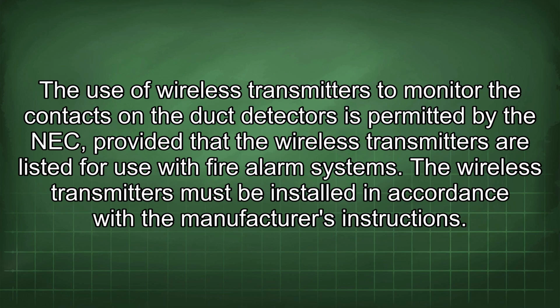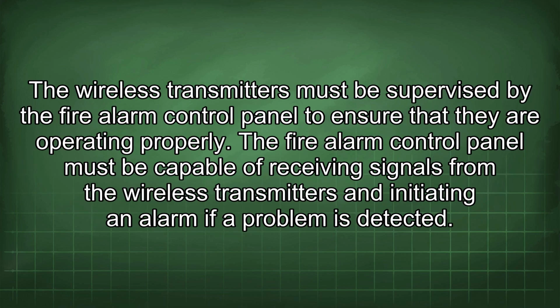The use of wireless transmitters to monitor the contacts in the duct detectors is permitted by the NEC, provided that the wireless transmitters are listed for use with fire alarm systems. The wireless transmitters must be installed in accordance with the manufacturer's instructions. The wireless transmitters must be supervised by the fire alarm control panel to ensure that they are operating properly.